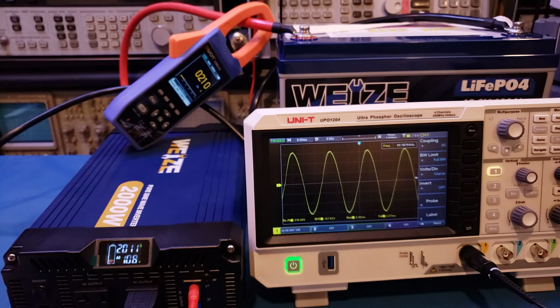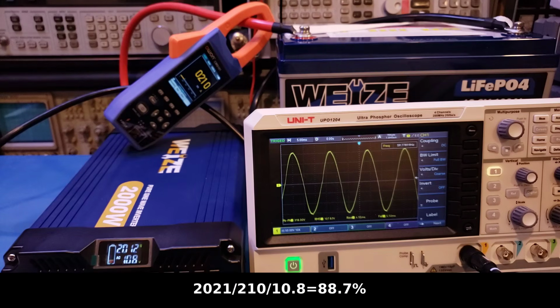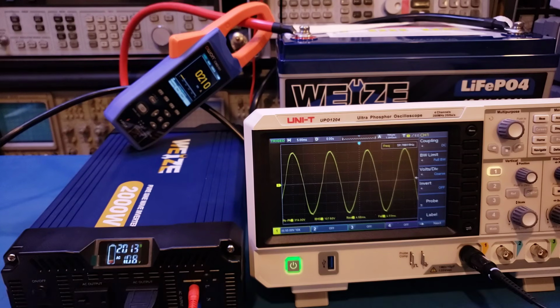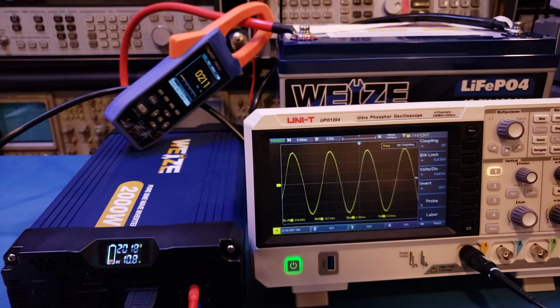I did a rough calculation of the inverter's efficiency at 2000 watts. Right now it's 10.8 volts, roughly 2000 watts, and the input current is 210 amps. Given these numbers, the efficiency is actually above 88%, which is quite good considering we're at maximum output power. The spec only specified the cutoff voltage at 300 amps for 5 seconds, so my guess is you could probably get away with a couple hundred amps for some time, as long as the BMS doesn't get too hot.